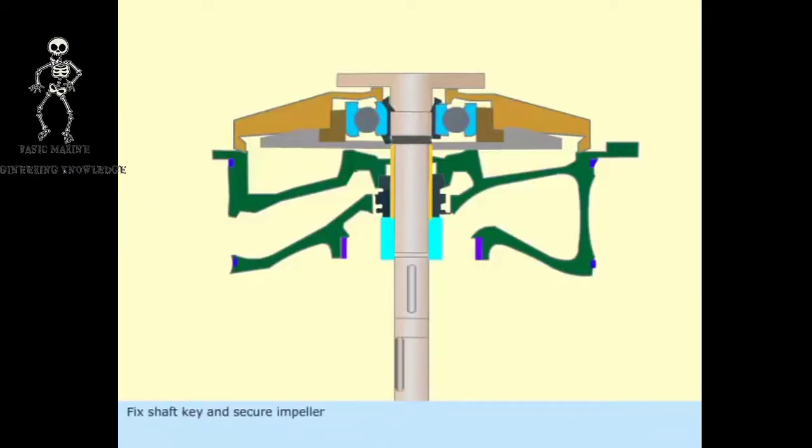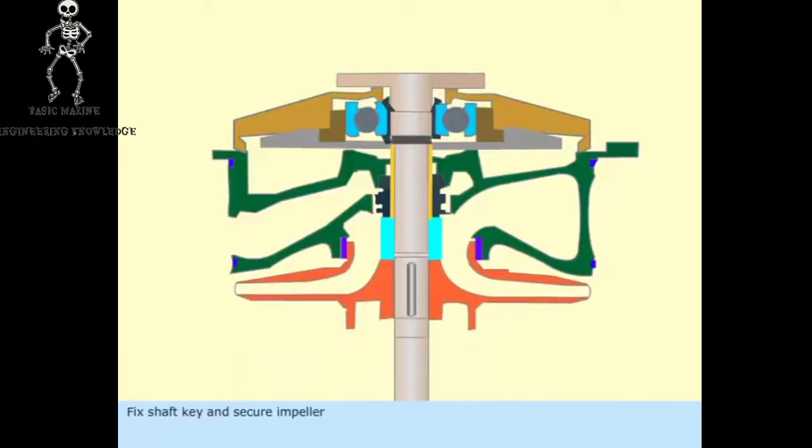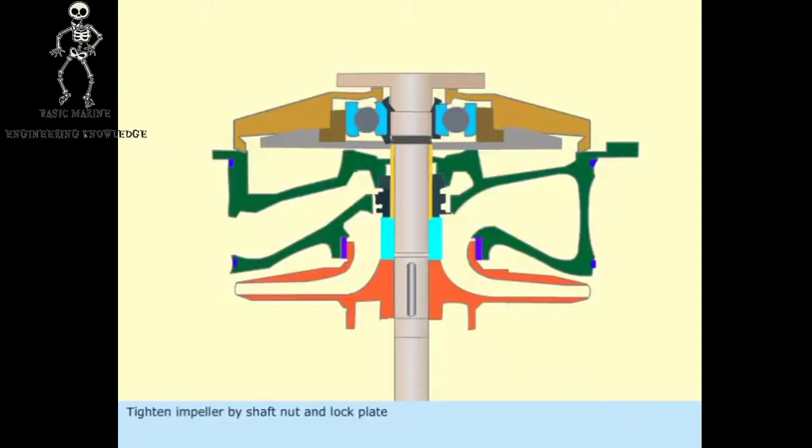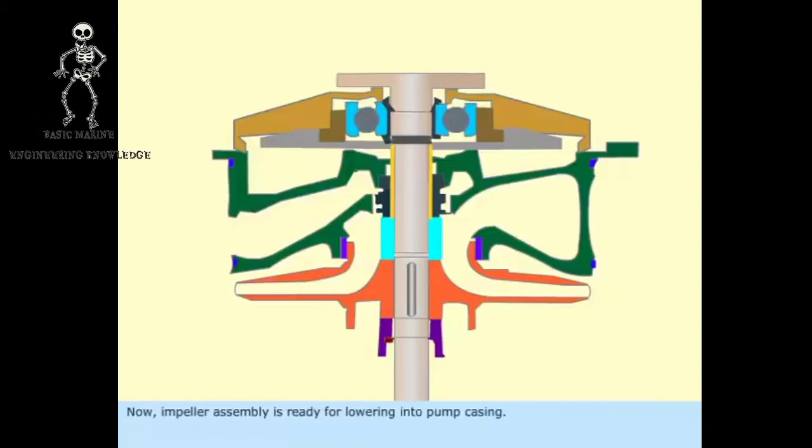Fix shaft key and secure impeller. Tighten impeller by shaft nut and lock plate. Now impeller assembly is ready for lowering into pump casing.